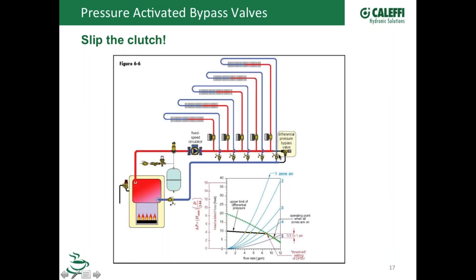Now, keep in mind, it is a bit of a parasitic device. Really what we're doing is shedding away excess head energy since we can't change the output of this fixed speed circulator. So it's important, I would say, whenever you have more than four zone valves, to consider a valve like this, even with a flat curve pump.